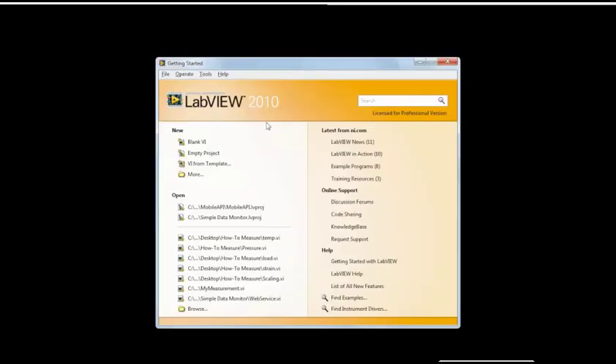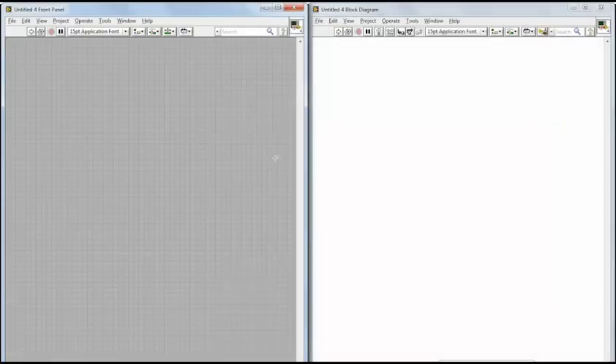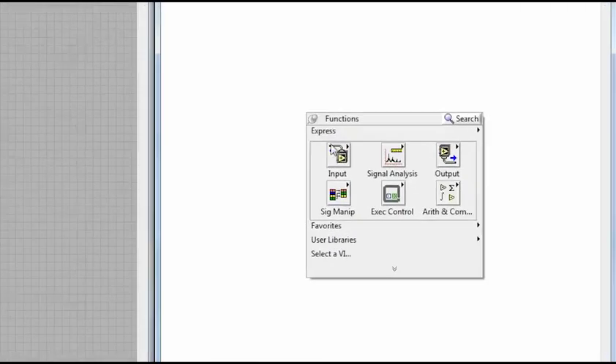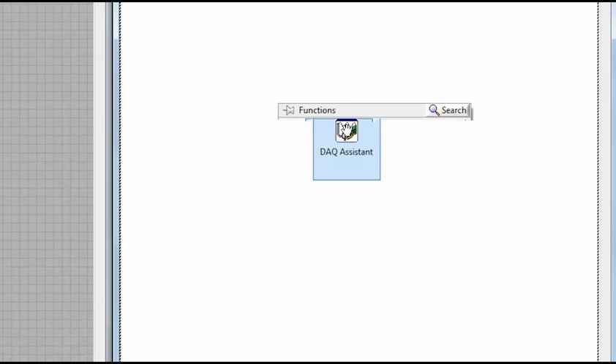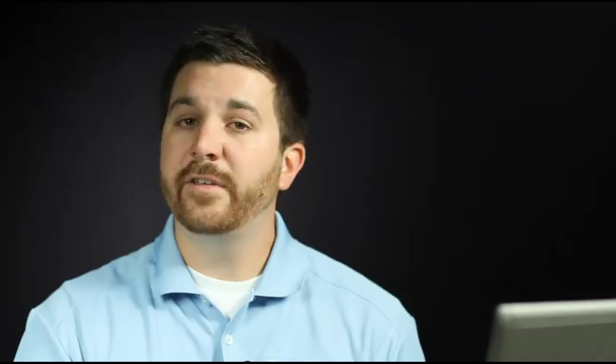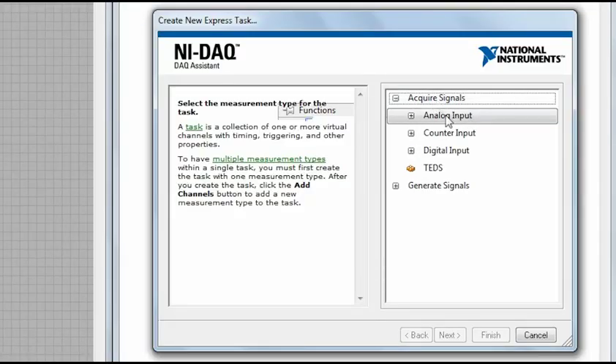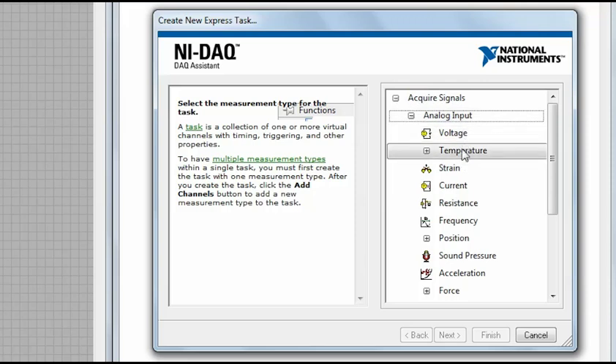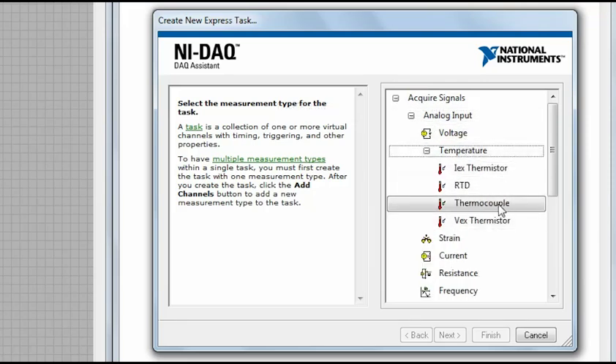And then I'm going to switch over to the computer here and launch LabVIEW and start a blank VI. And over here on the block diagram, I'll right-click, go to input, and we're going to add a DAQ assistant. And so this is a step-by-step wizard that allows me to set up my measurement. So we're going to choose Acquire Signals, Analog Input, Temperature, and we can see the setting for thermocouple here.